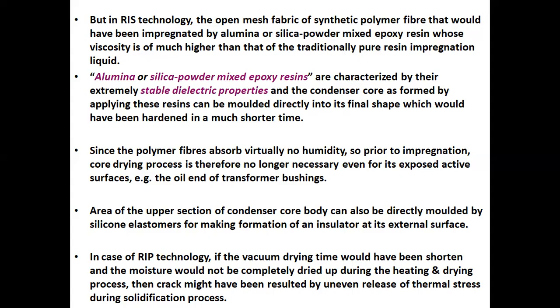Since the polymer fibers absorb virtually no humidity, a drying process prior to impregnation is no longer necessary, even for the exposed active surfaces, for example the oil end of transformer bushings. That is, it is time saving. Its manufacturing purpose is time saving. The area of the upper section of the condenser core body can also be directly molded with silicone elastomers to form an insulator at its external surface.